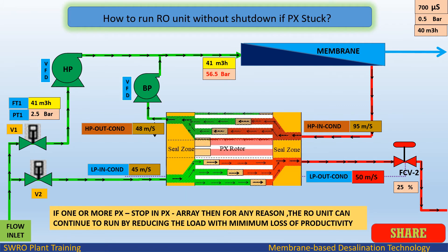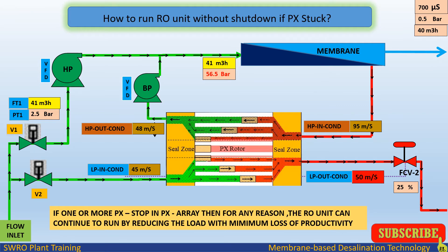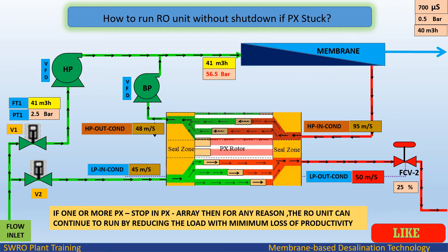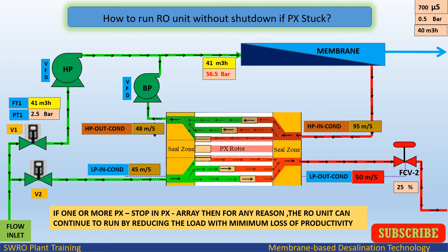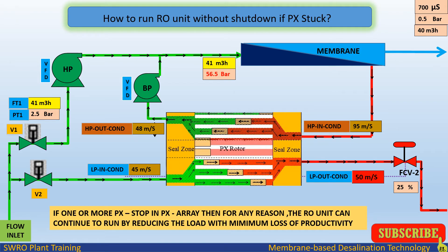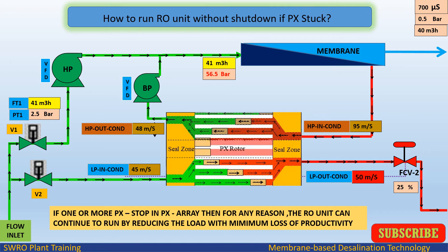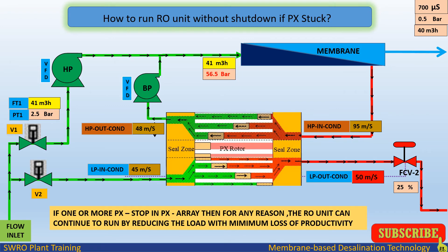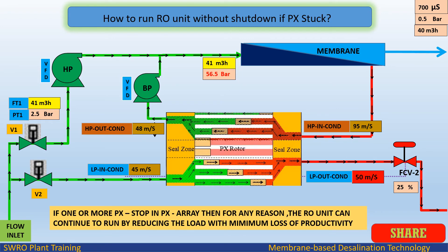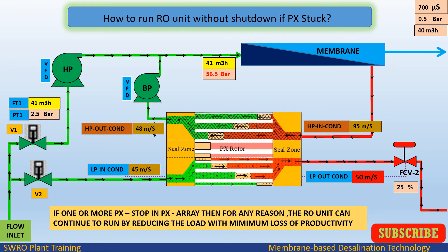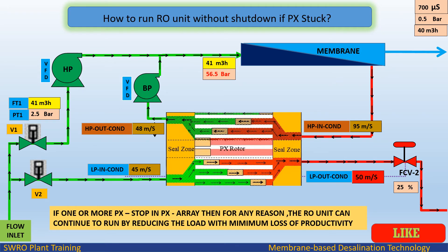How to run the RO unit without shutdown if PX is stuck: if one or more PX stop in the PX array for any reason, the RO unit can continue to run by reducing the load with minimum loss of productivity.